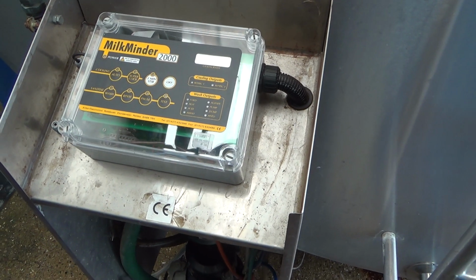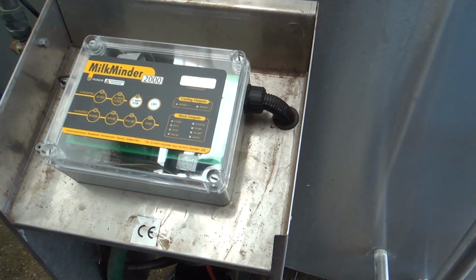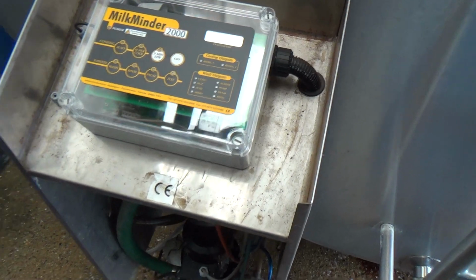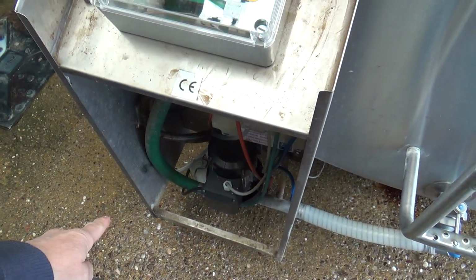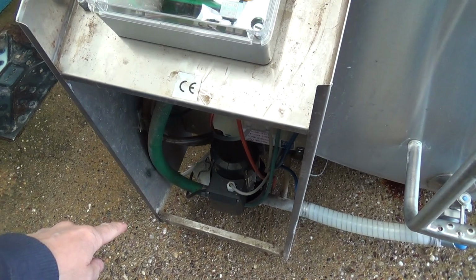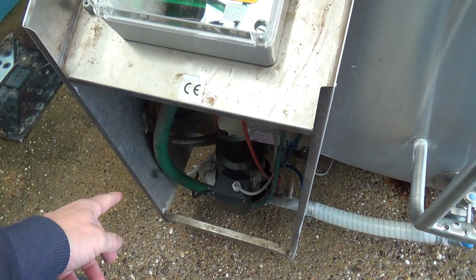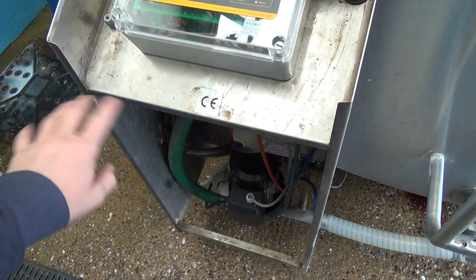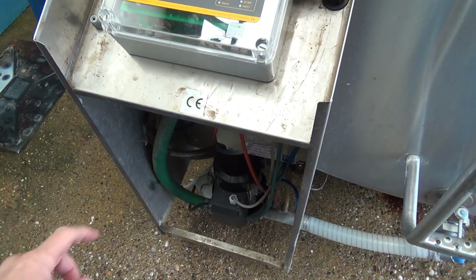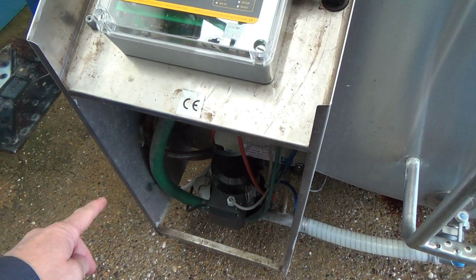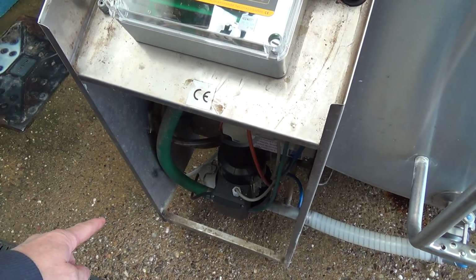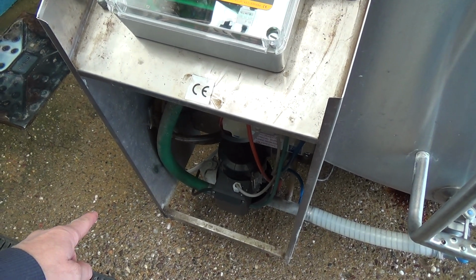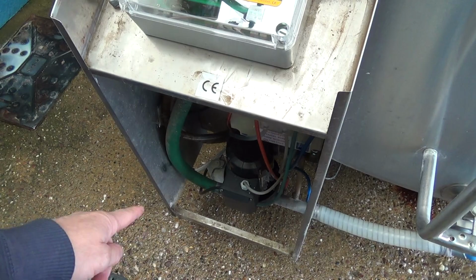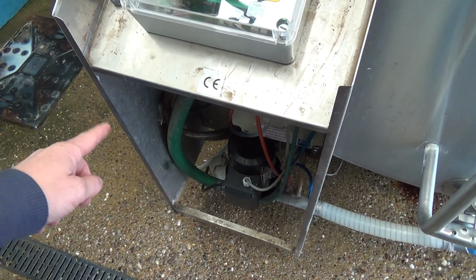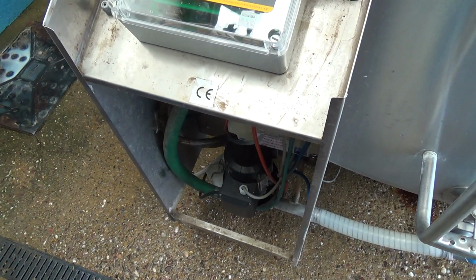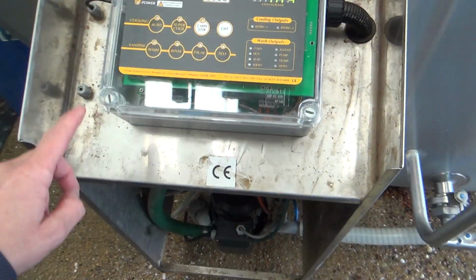Okay, having a look at this Fabdec DX milk tank. Customers reported it's tripped the power out. It's a bit vague whether it's the RCD, or an earth leakage fault, or whether it's just the current trip. I doubt it'd be the current trip because this is run off a control panel that also feeds 2 compressors. So I think the tank is fused down from that, but that's going to have some big 30 amp 3-phase supply going into it, so it's probably not that, so it's probably the RCD.